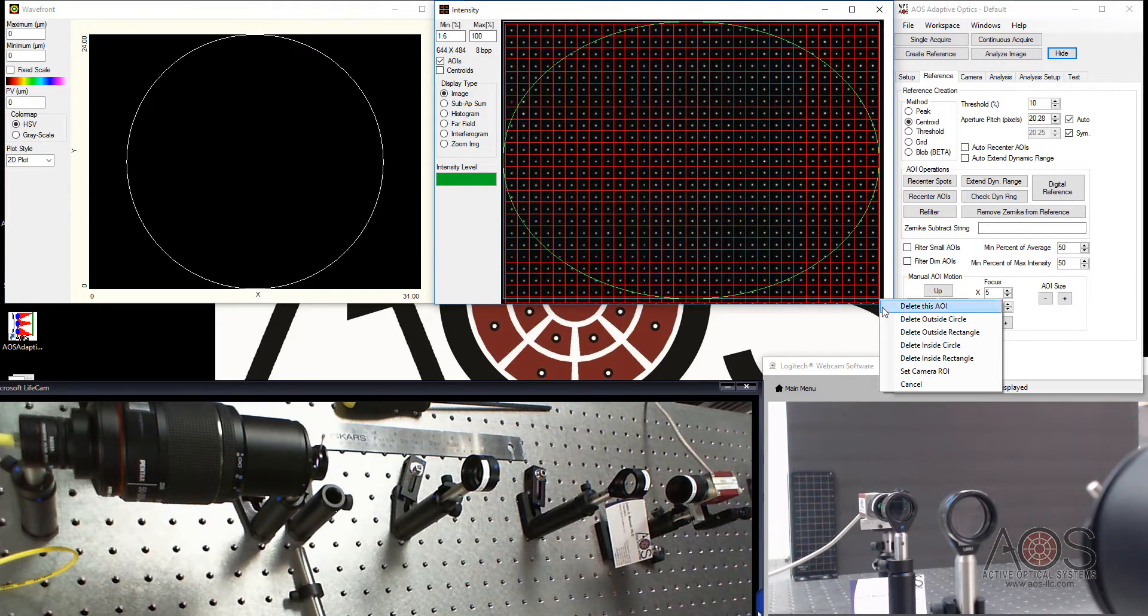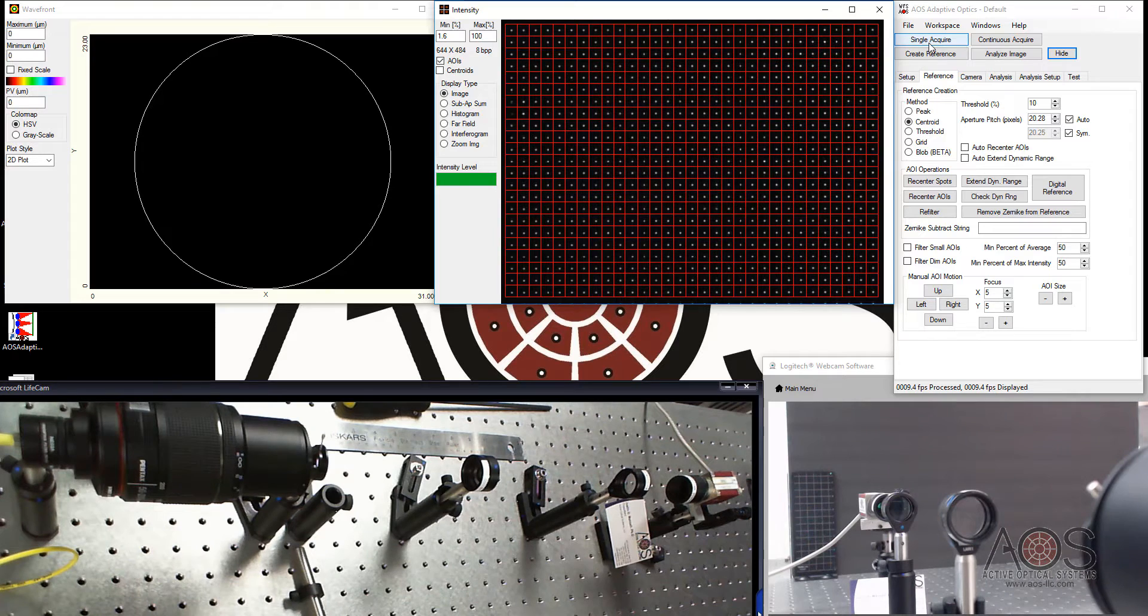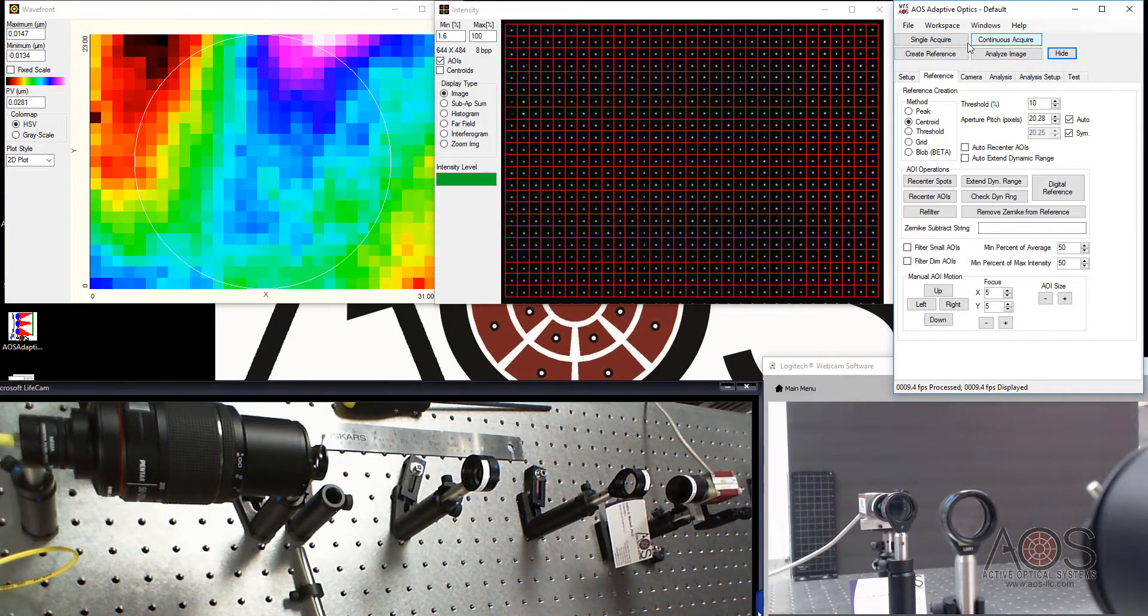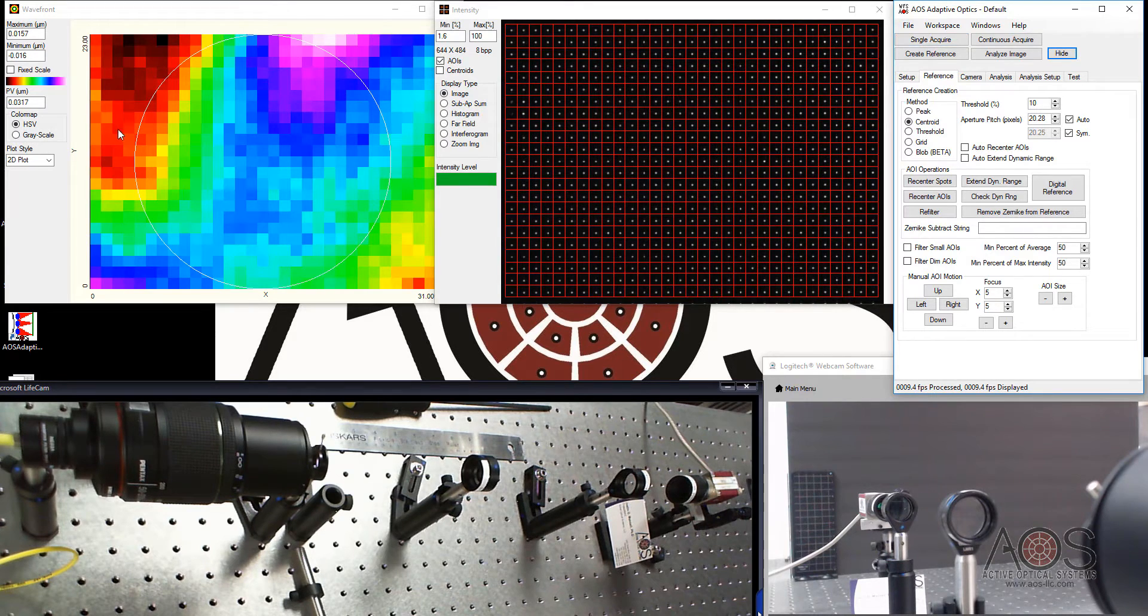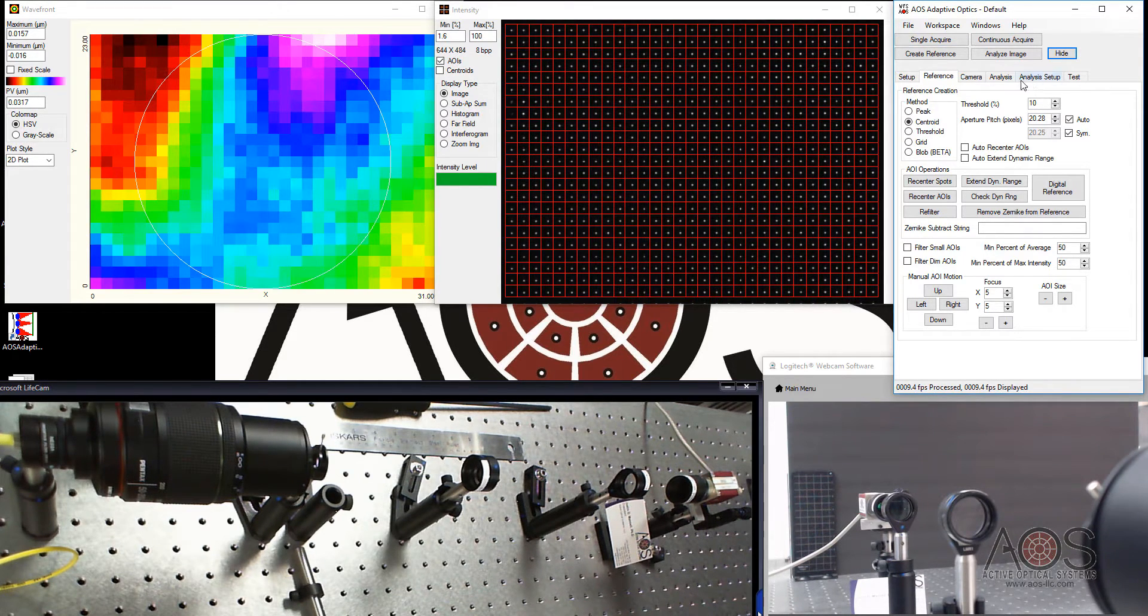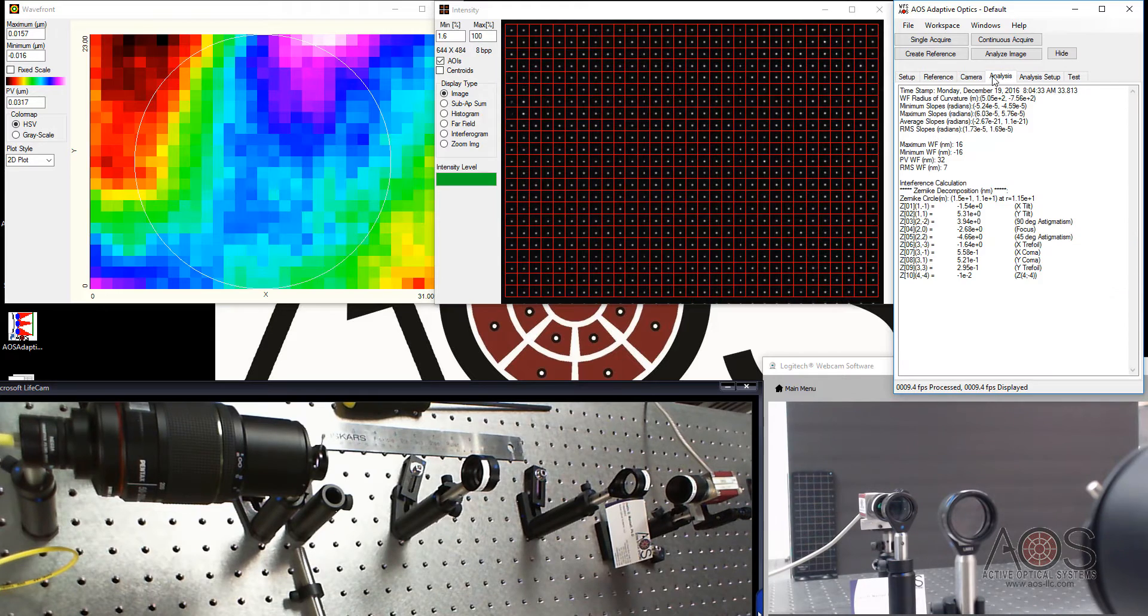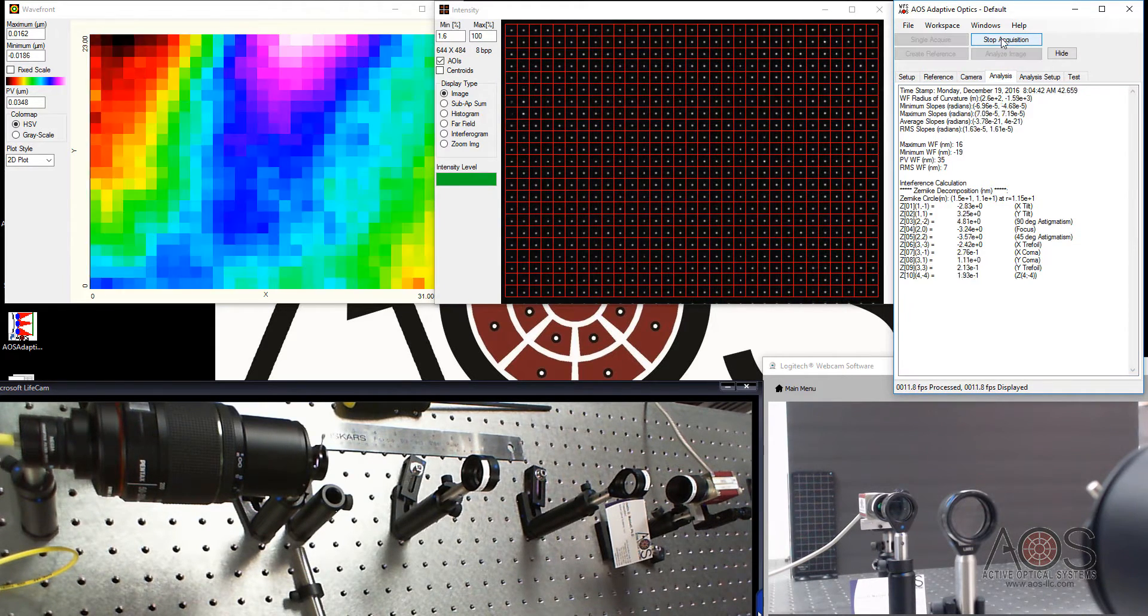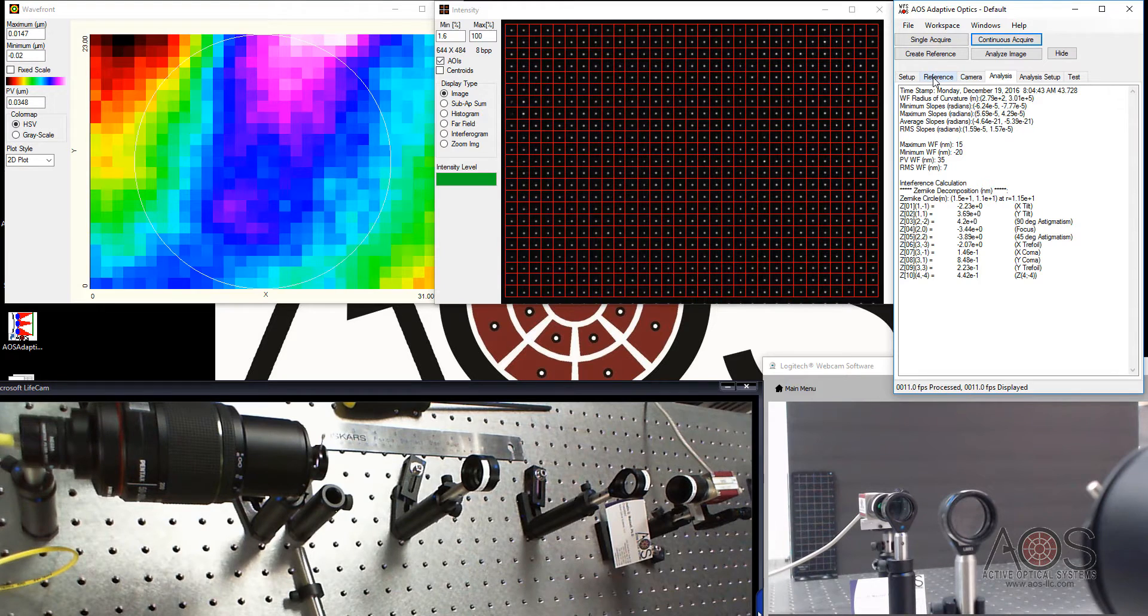You can also just click the create reference button and go in here and eliminate any ones that you don't like. Right click and drag, release the button and say delete outside rectangle. So I'm going to go single acquire. And now I'm back down to a pretty good condition here. 30 nanometers peak to valley. Sort of the noise on this. We're seeing about 7 nanometers RMS. Looks pretty good.